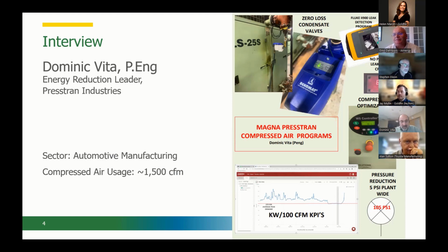And in terms of the savings in this kind of setup, is the main thing coming from being able to reduce that pressure of the initial one because it's not the cascading bands, or with their setup, like they have three fairly similar sized compressors? In terms of would there be much savings from optimizing the sequence or order that those come on?